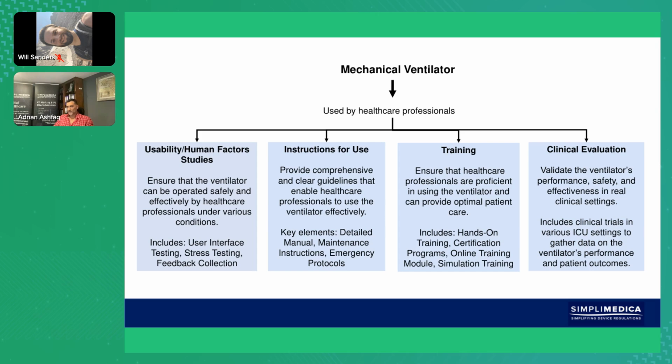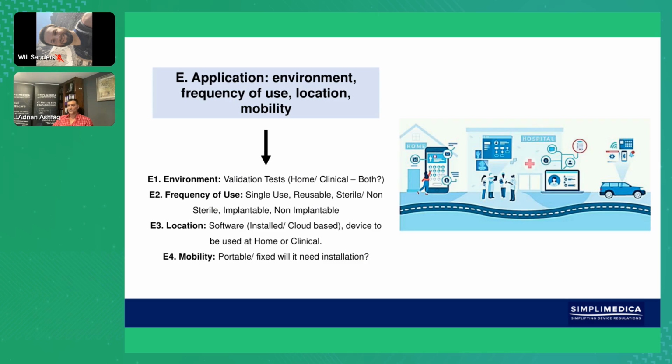If you have no experience with medical devices, it can be very overwhelming to get involved, so try to do things the simpler way, the easier path to regulatory conformance. Once you've achieved regulatory conformance, and that could be through a 510(k), or through self-declaration in Europe or the UK, and you have some experience of doing that, you can then use very much the same content for submitting a file to a higher classification with higher claims, with more bells and whistles added to it. So it's a stage-by-stage strategic process. That's often my advice.